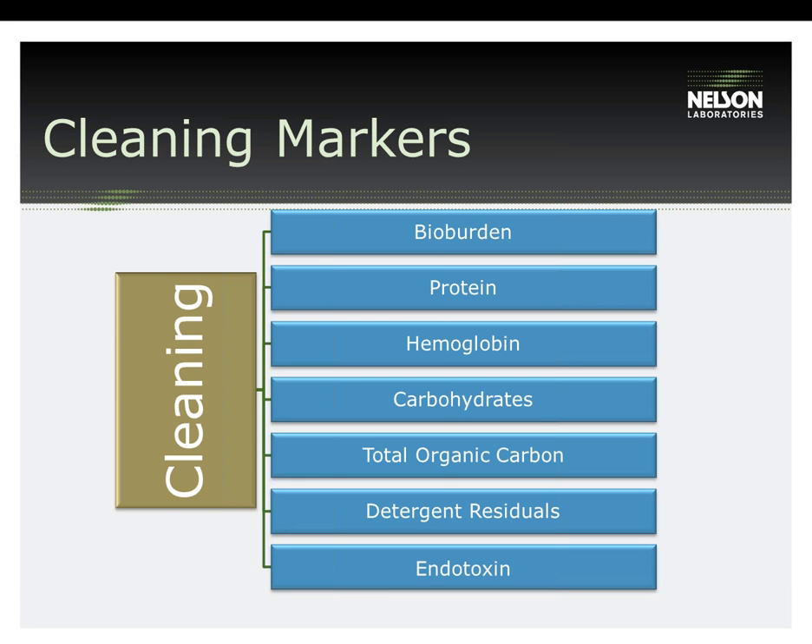Once the devices are extracted, the extracts are analyzed for a number of tests which we call residual testing cleaning markers. These markers are listed in TIR30 and the selection of what markers should be tested depends on what your device is coming in contact with and what would be suitable for your test plan. Not all cleaning markers need to be validated — you want to choose what will be applicable for your product. At least two cleaning markers are recommended for the validation. Protein is the number one marker and is usually accompanied by TOC or carbohydrate, which has been the current trend. Keep in mind that TOC does not have acceptance criteria outlined in TIR30, so the reasoning for using this marker would have to be justified by the manufacturer.